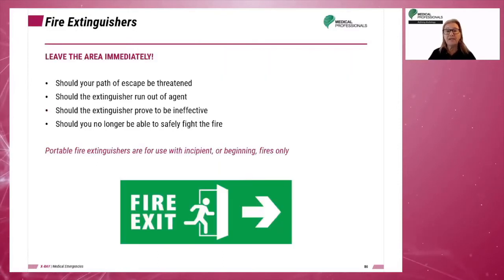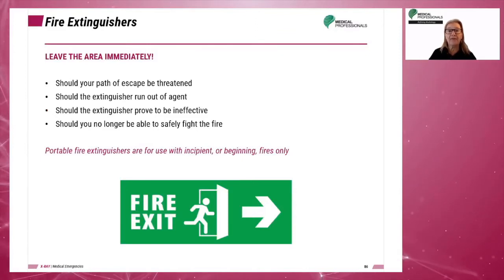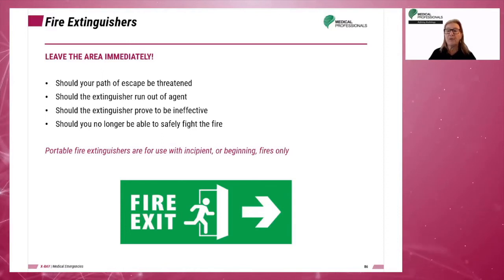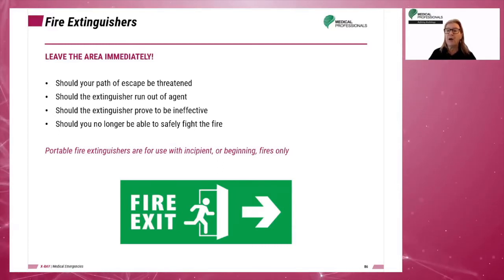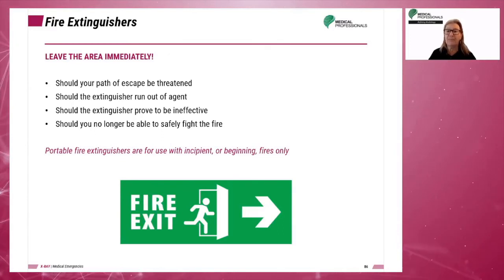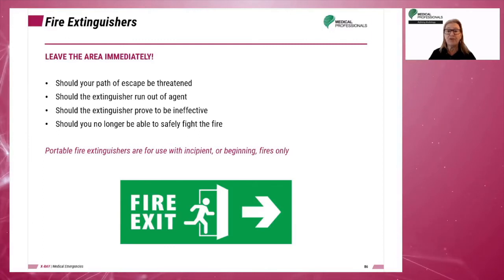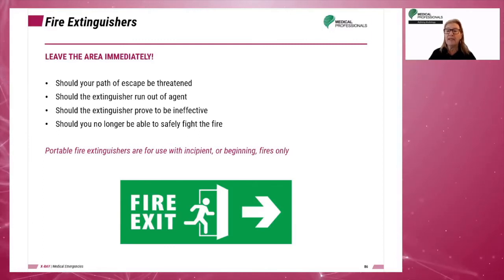In case of a fire, you should leave the area immediately if your path of escape is threatened, or the extinguisher runs out of agent, or the extinguisher proves to be ineffective, or if you are no longer able to safely fight the fire. Remember that portable fire extinguishers are only for incipient or beginning fires.